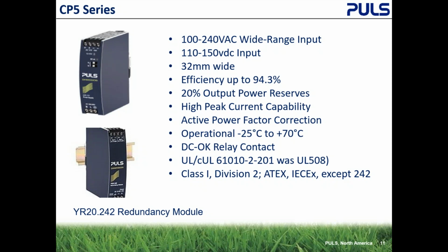So the 5 amp will put out 6 amps continually. The caveat is the temperature is between -25 and plus 45 C. At those temperatures, it will put out 20% more. At 46 C up to 60, we recommend staying at a 5 amp just because of the heat buildup. You can see the efficiency is higher than our CS. The active power factor correction is added. It also has a DC OK relay contact, which the C series does not.